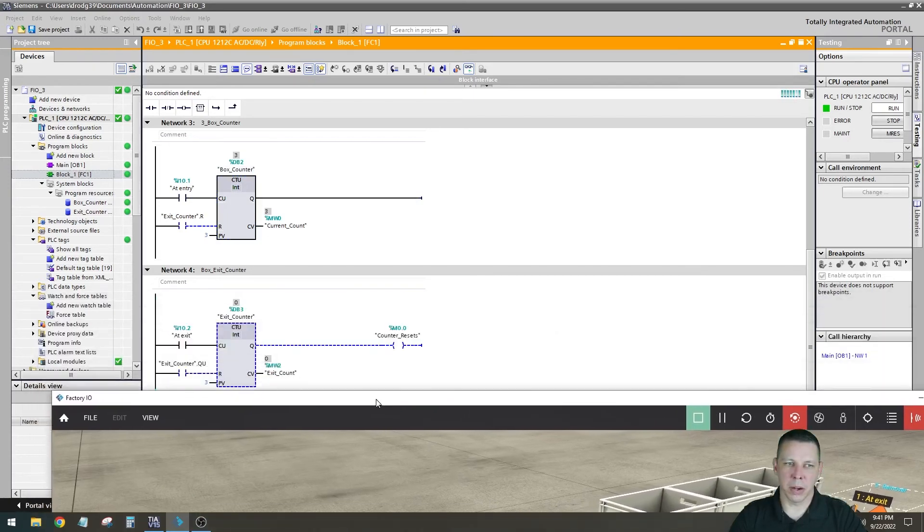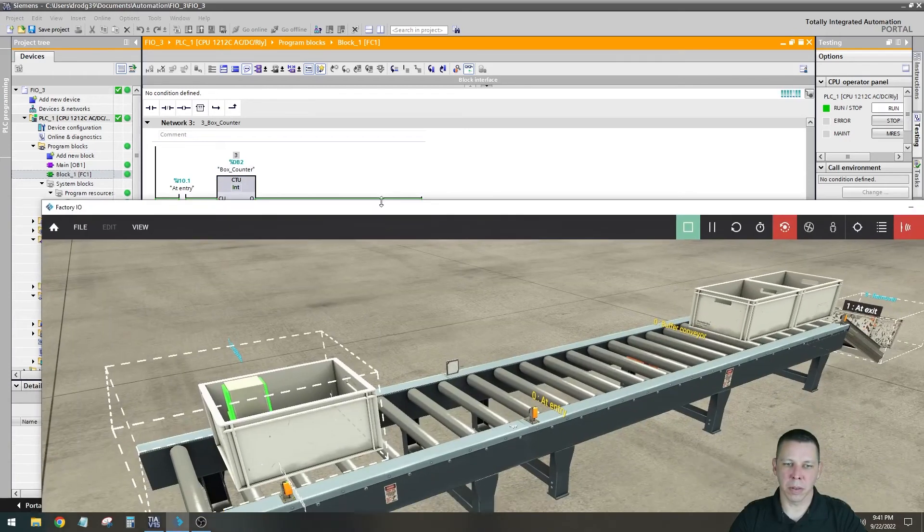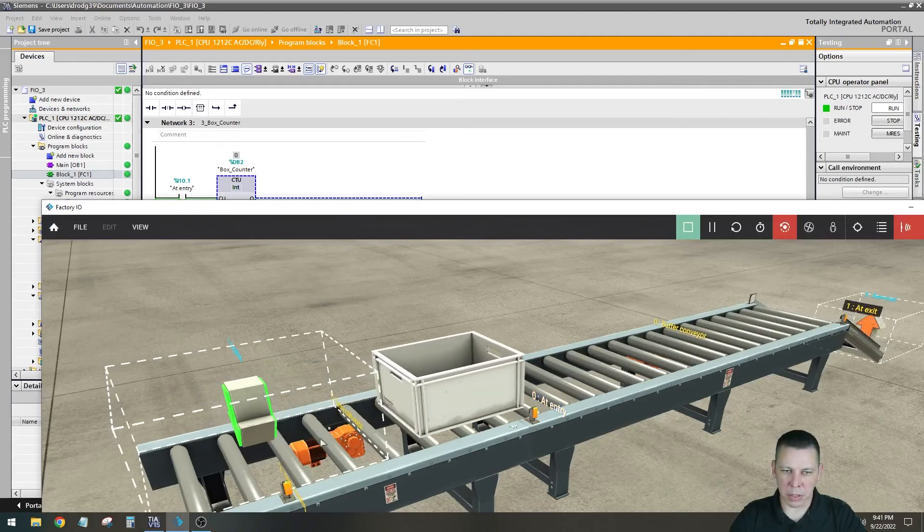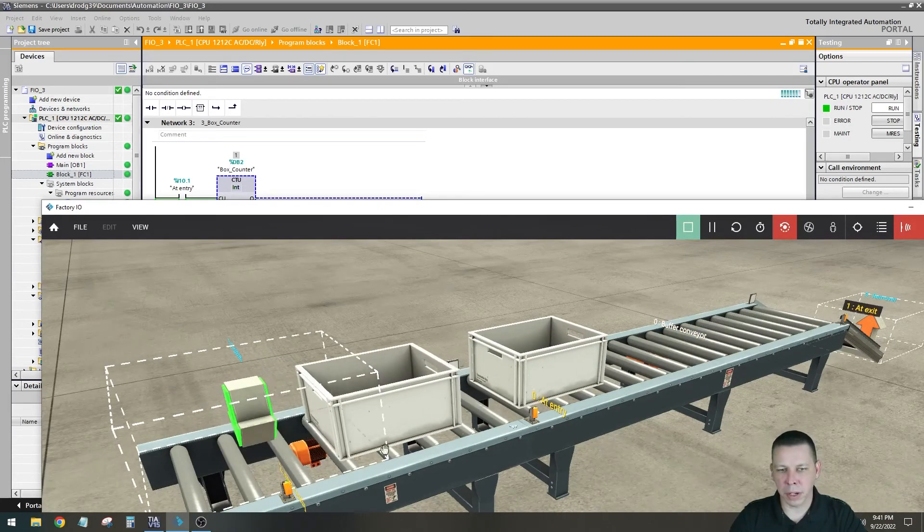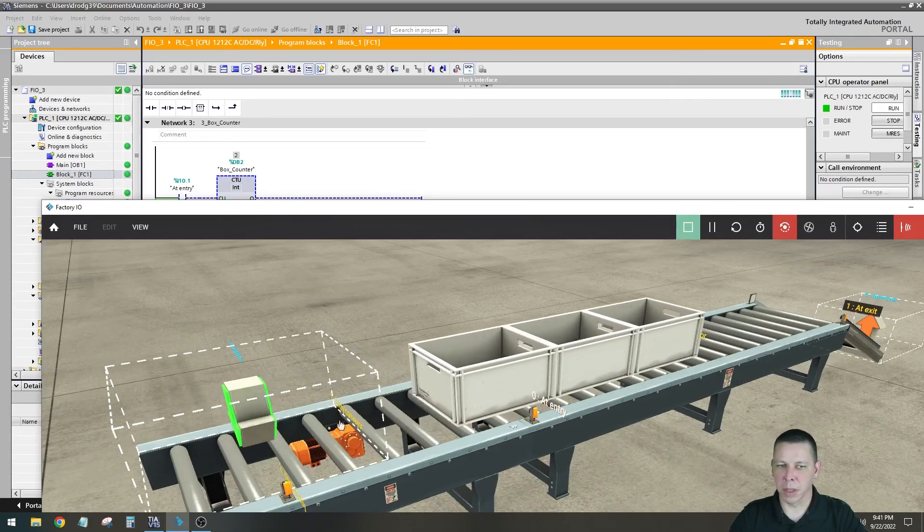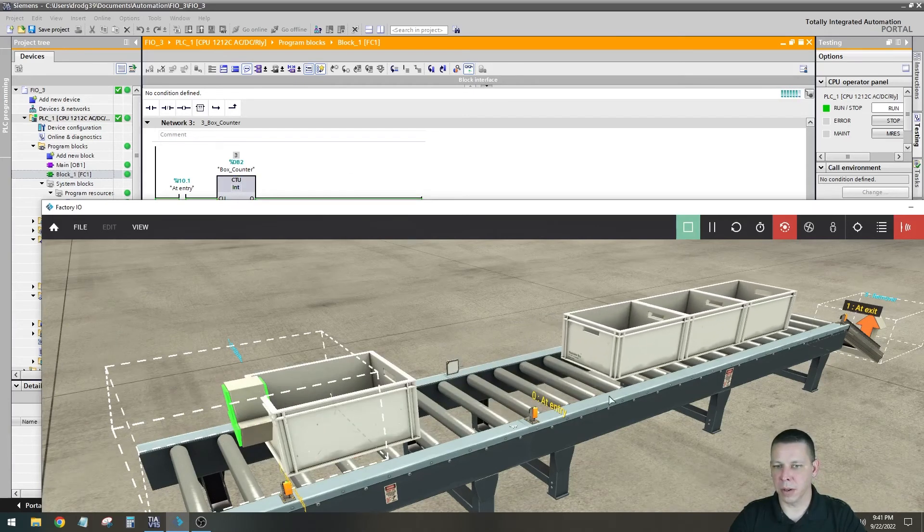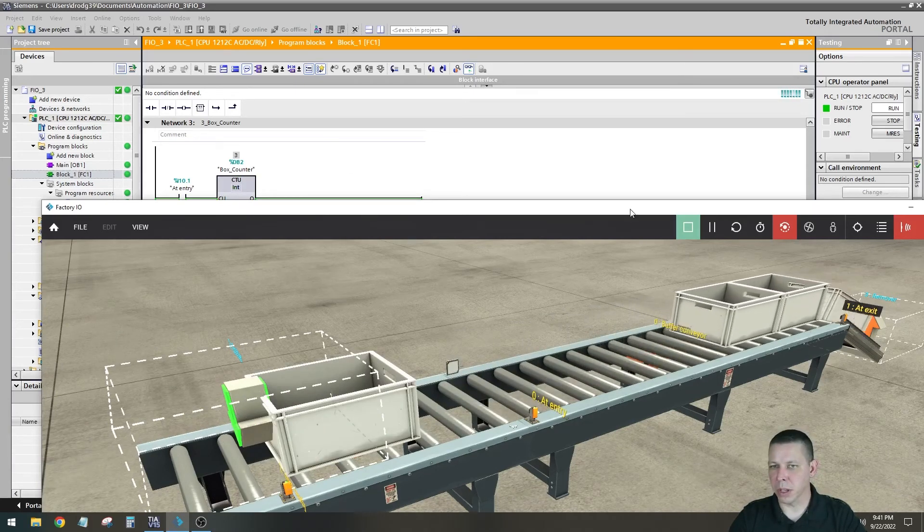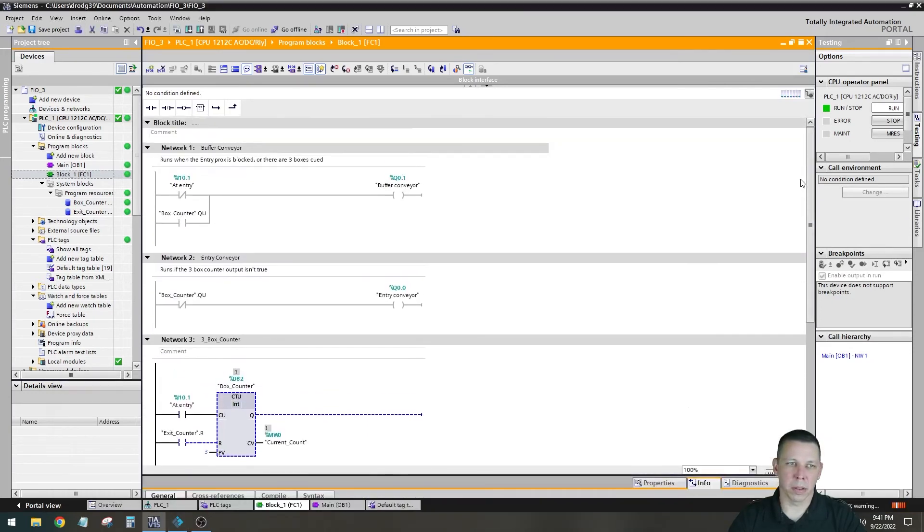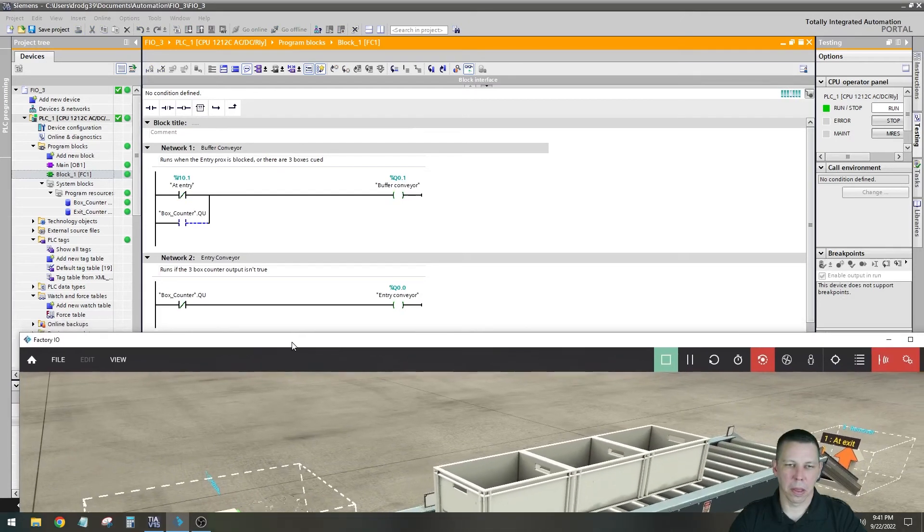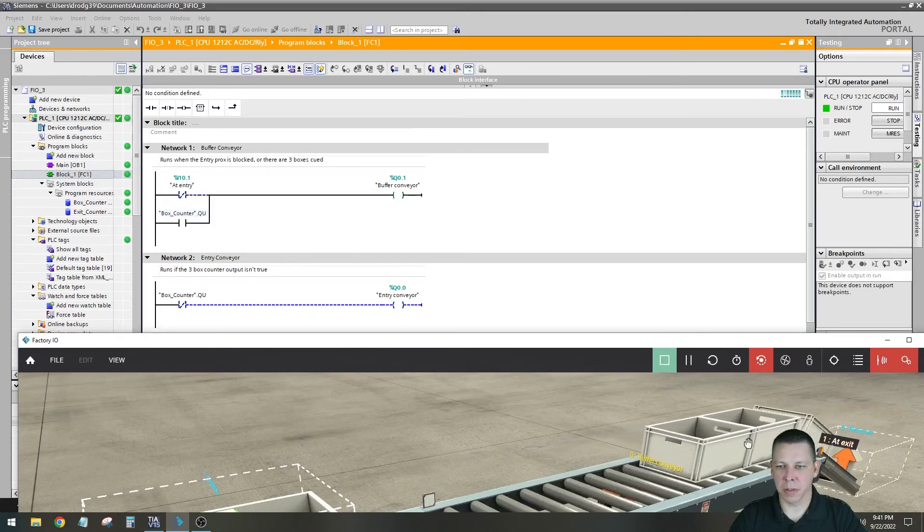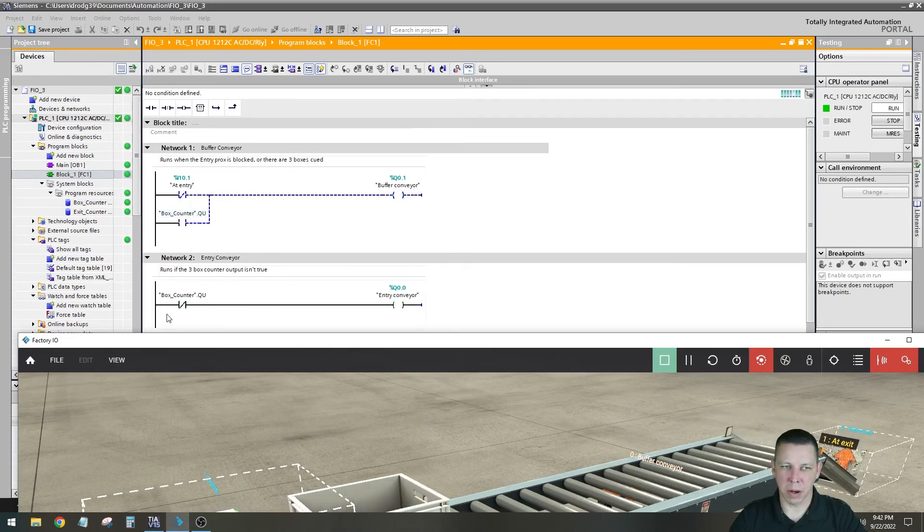So when that energizes it stops the infeed conveyor. This conveyor here. It stops this entry conveyor they call it here. So once this counter that's counting going past here, it counts to three, it'll stop this conveyor and then it'll latch around up top to keep this one on until this one counts to three, which is this bottom one. Then you know that all three are off there. Then everything resets and it goes back. And again it looks like this up top. So now because it counted to three it latches around there and it keeps this conveyor running the whole time until that other one counts to three and then it resets this counter.